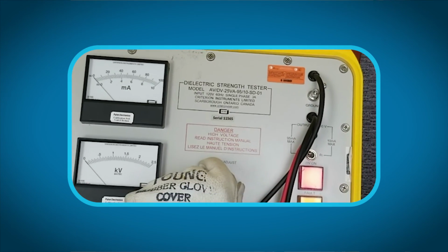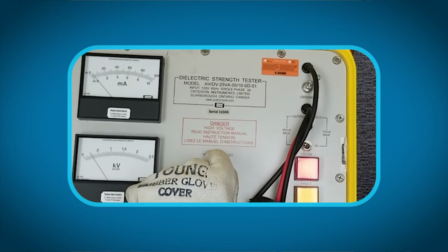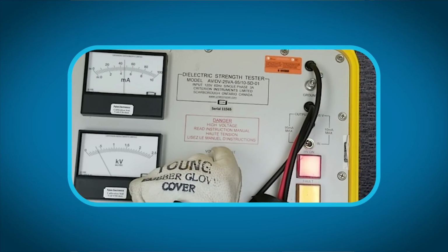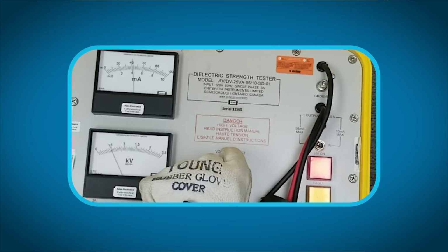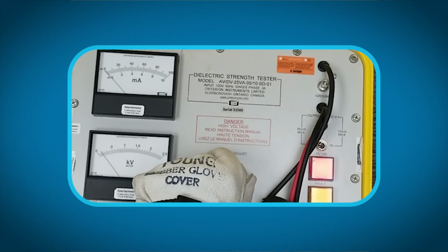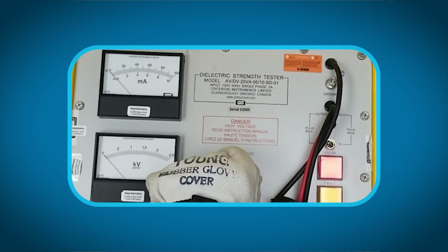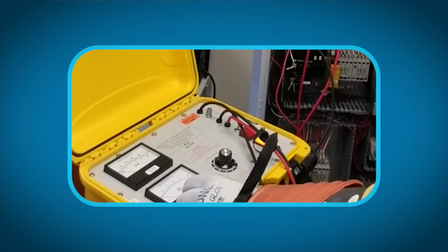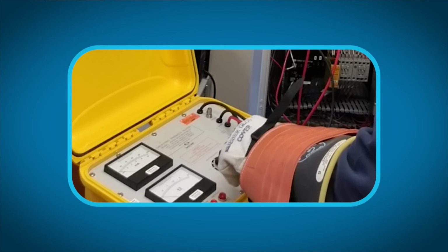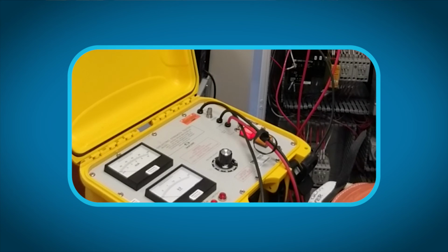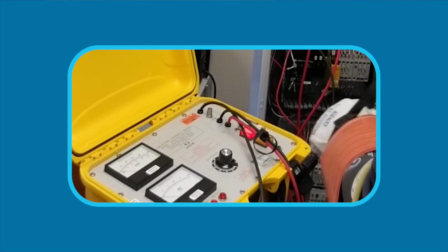Insulation breakdown is considered to have occurred when the current which flows because of the application of the test voltage rapidly increases in an uncontrolled manner, and the insulation does not restrict the flow of current. Current discharge or a single momentary flashover is not regarded as an insulation breakdown.